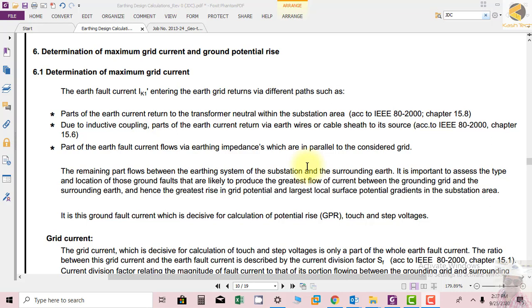Due to inductive coupling, part of the earth current returns via earth wires or cable sheath to its source, according to IEEE 80-2000 Chapter 15.6. The earth current through the cable sheath can also return back to the source, so the sheath is another return path for earth fault current.